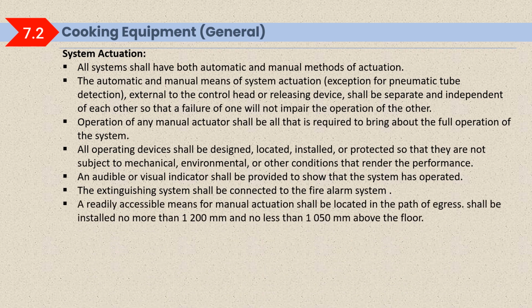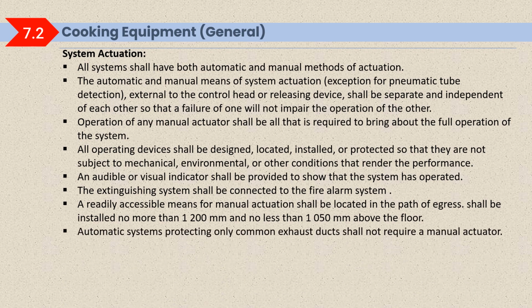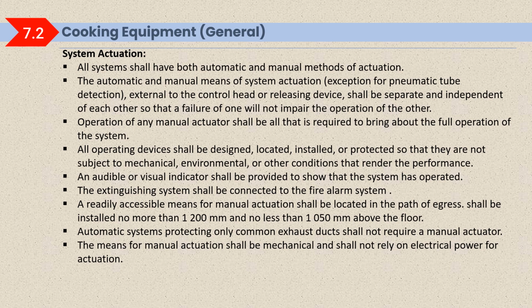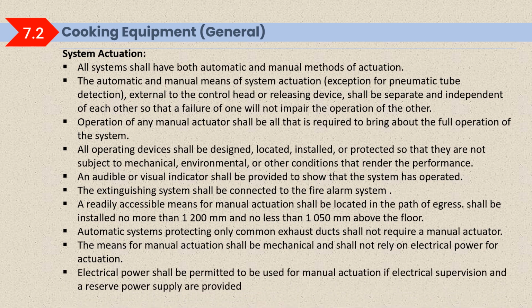A readily accessible means for manual actuation shall be located in the path of egress and shall be installed no more than 1200 mm and no less than 1050 mm above the ground. An automatic system protecting only a common exhaust duct shall not require a manual actuator. The means for manual actuation shall be mechanical and shall not rely on electrical power for actuation. Electrical power shall be permitted to be used for manual actuation if electrical supervision and a reserve power supply are provided, like a UPS supply, then it is acceptable.